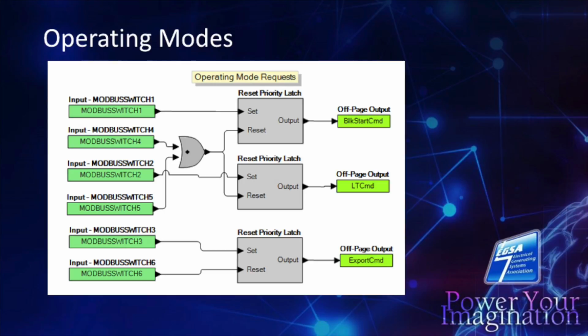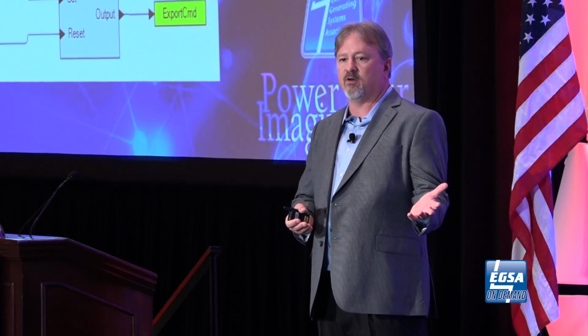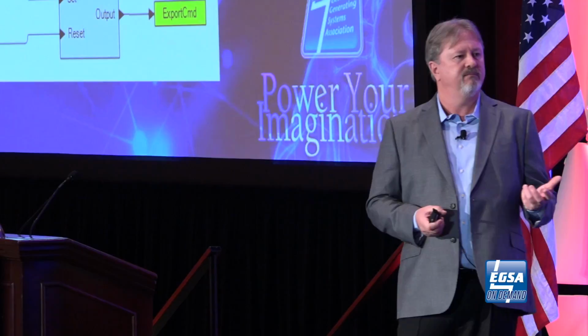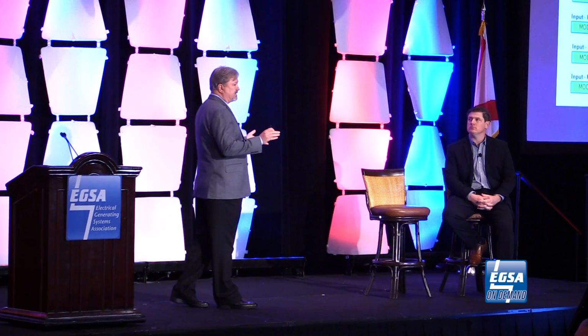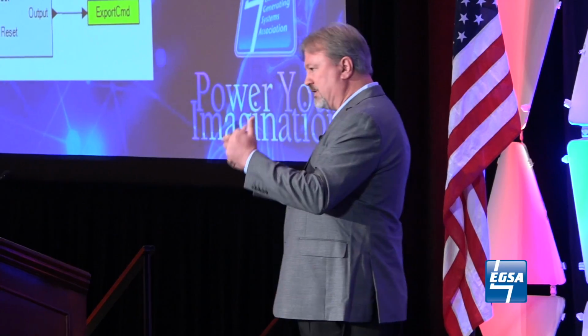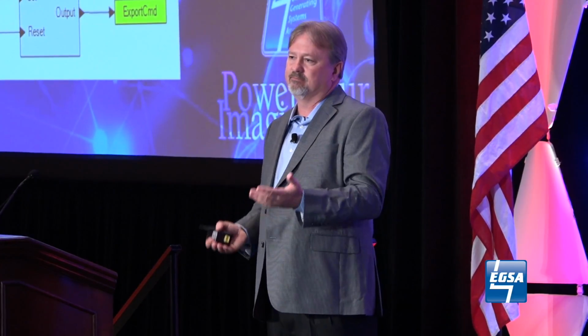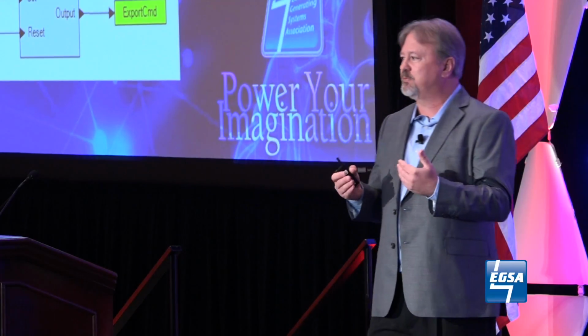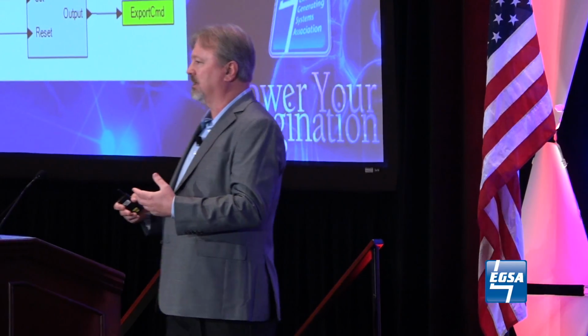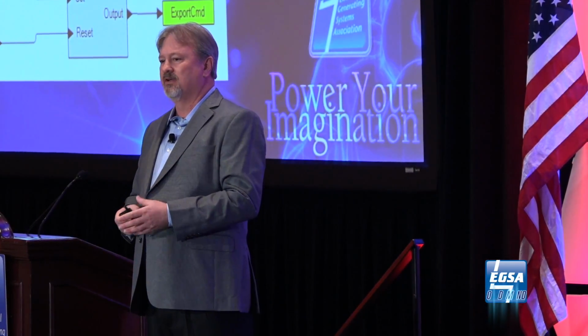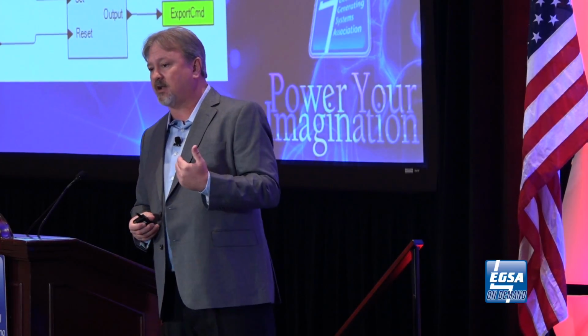So for the black start, we don't actually start the generators. We don't sense the utility fail and start the generators, which is a normal operation for our controllers. What we do is they have a DeltaV, that's basically a PLC monitoring the plant status. So we send Modbus signals to that. We sense the bus failure on the utility side, whether it's through the 81 over/under frequency or the 78, or it just goes dead, unstable. We send that status to the DeltaV. The DeltaV returns us a black start command, which we could have done all of that ourselves, but this lets the switchgear builders think that they have some control in it. And it kind of alleviated some tension about who was controlling when we were starting and stopping.